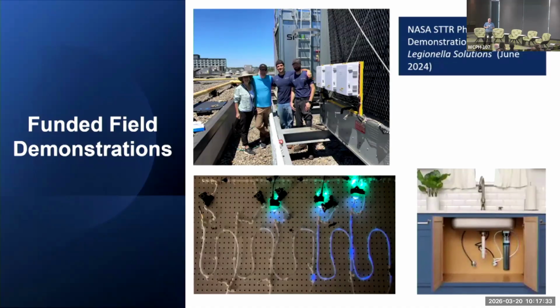The cooling tower uses all types of chemicals, including chlorine, but they still have detectable hits of Legionella in the water. That's because as the cooling tower water in the basin goes up and down, when it's down, the biofilms on the wall grow; it comes up, shears them off, and then gets aerosolized. That leads to violations as well as additional chemical needs.